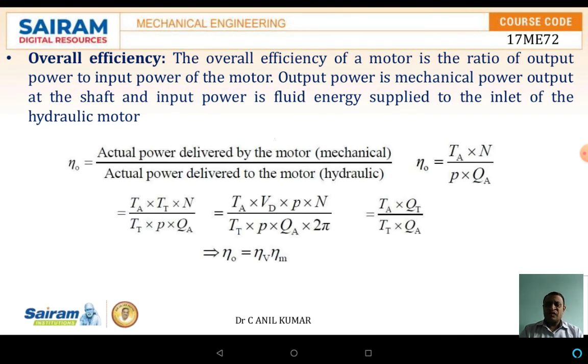The overall efficiency of the motor is the ratio of the output power to the input power of the motor. The output power is the mechanical power at the shaft, and the input power is the fluid energy, which is the pressure. In simplified form, the equation is: overall efficiency = T_A × N / (P × Q_A).